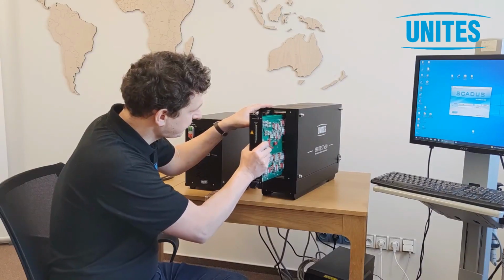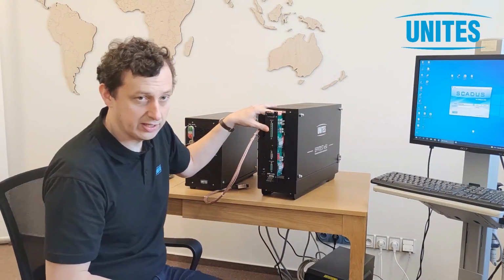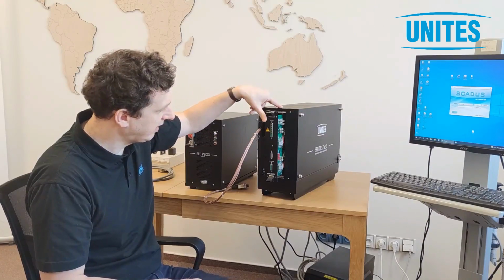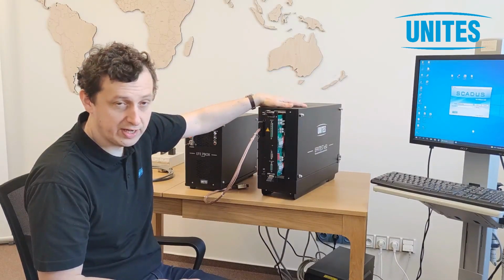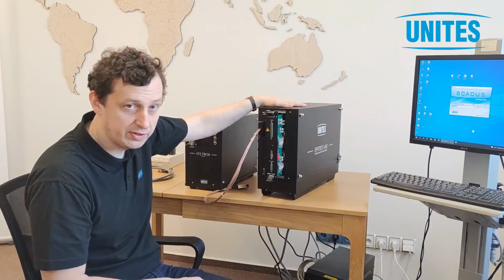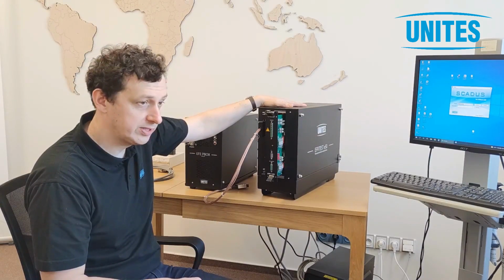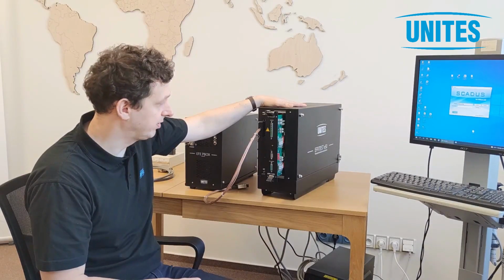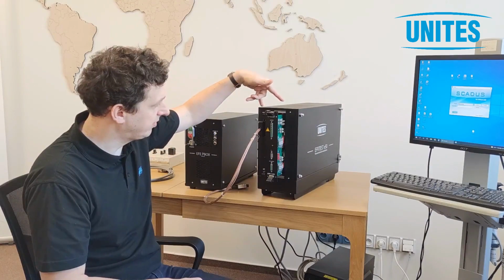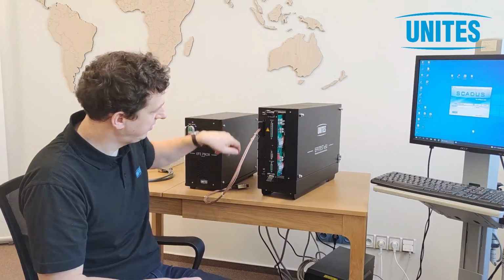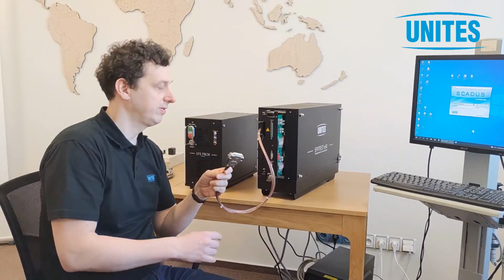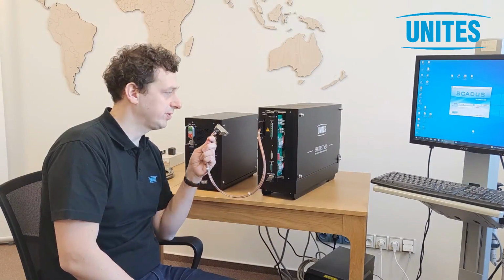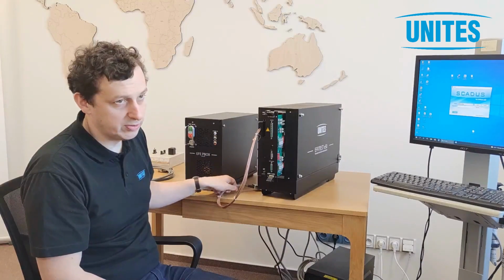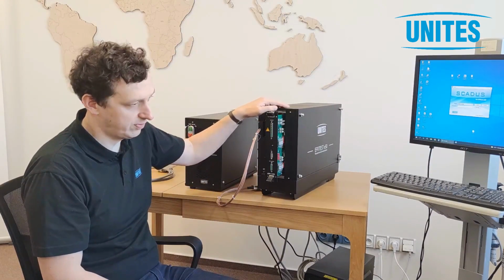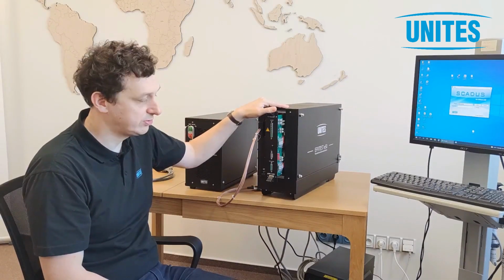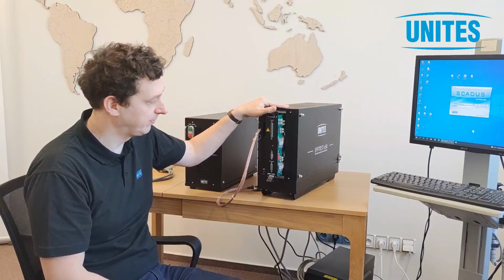One CVI can test one test position on the handler, and today I have two CVIs here, the model called Effitest E50 Dual, which is capable of testing in serial or parallel mode. This means you can connect each CVI to one test position, test position one or test position two, and you can either test the same component, half on position 1 and half on position 2, or test two devices simultaneously in parallel mode.